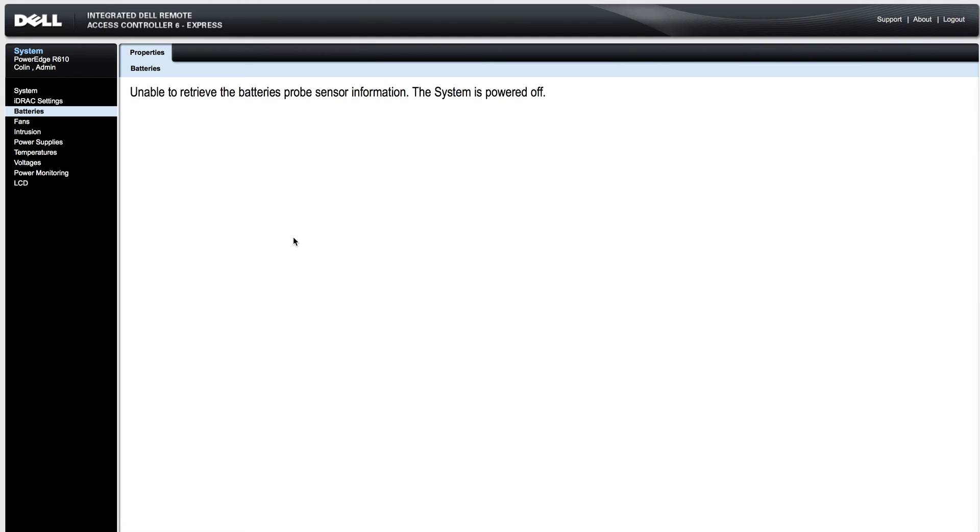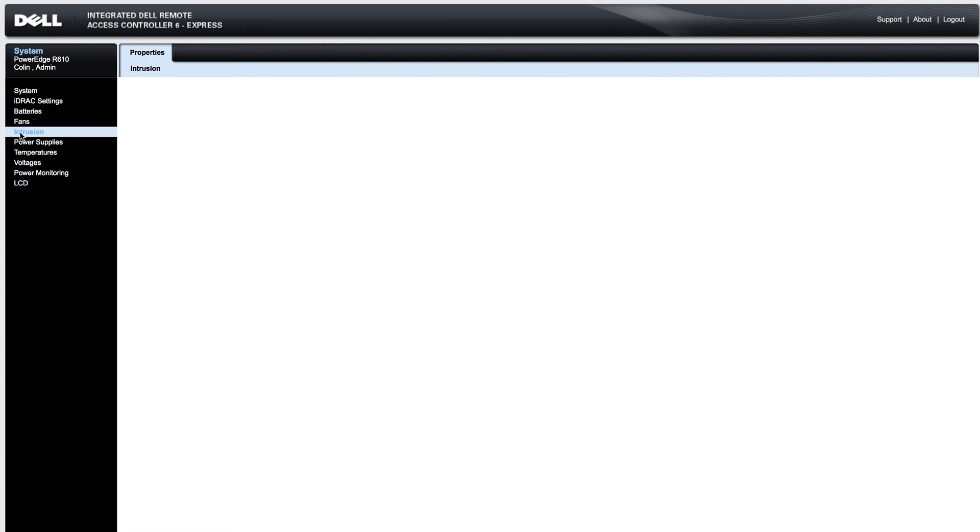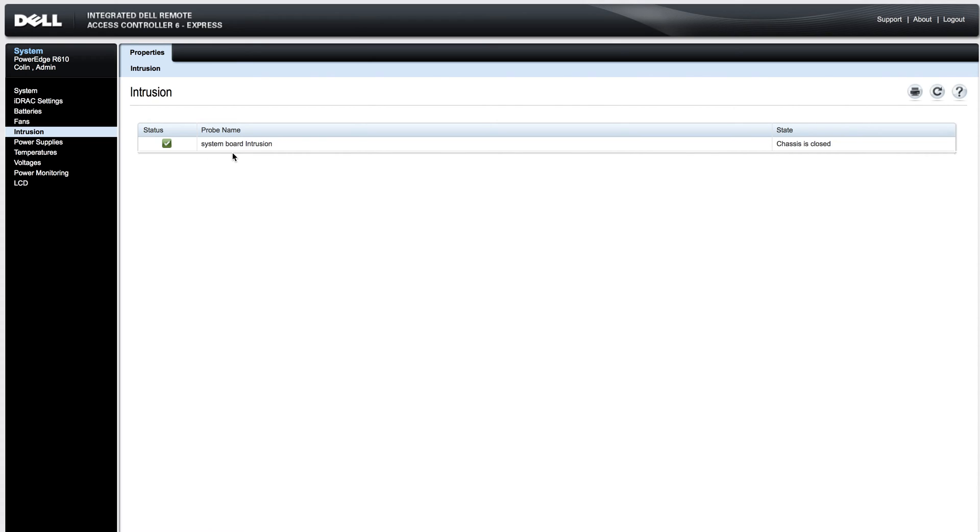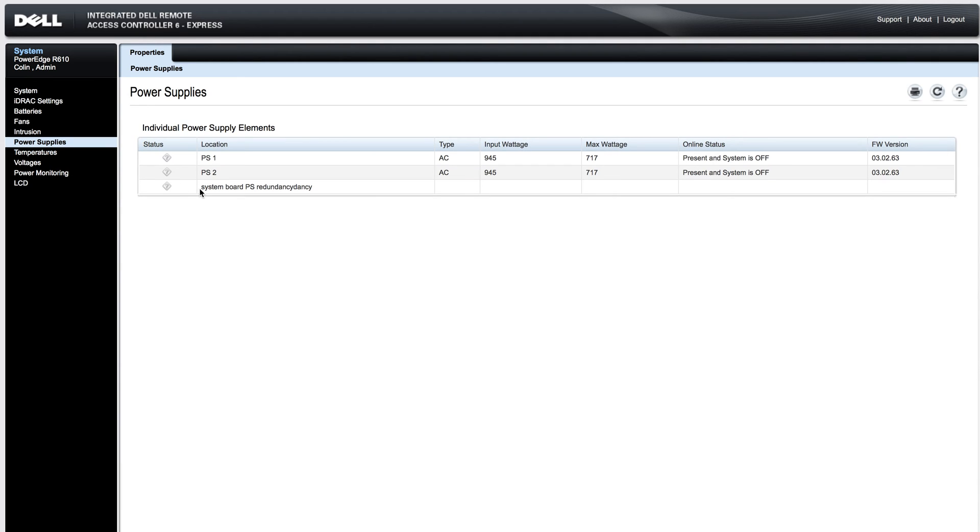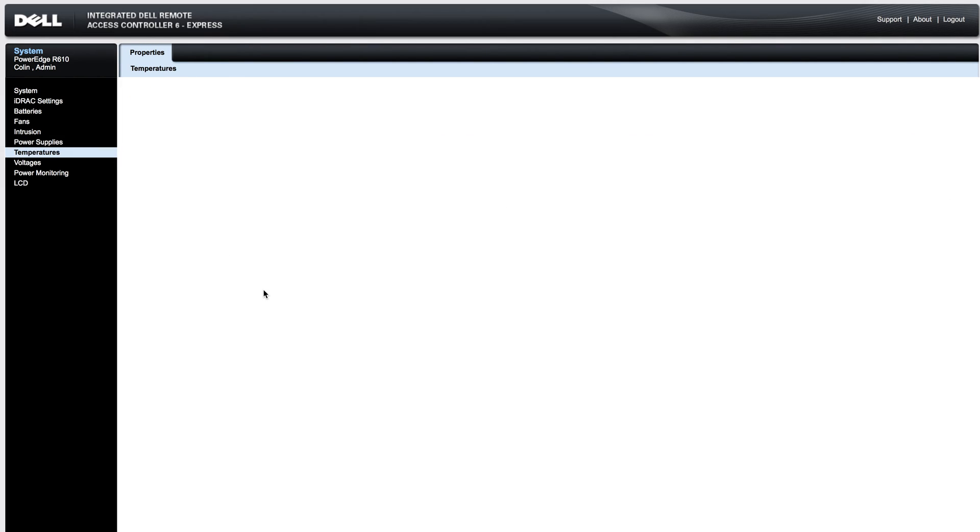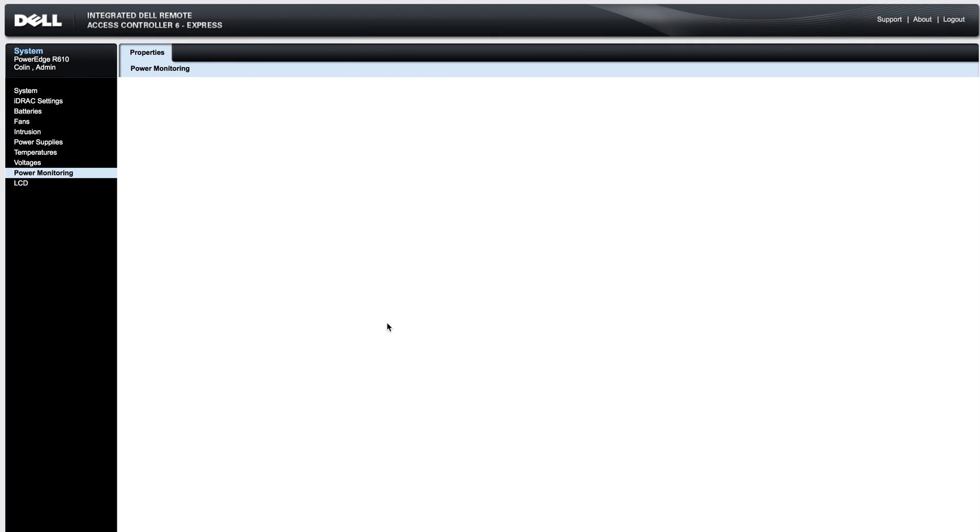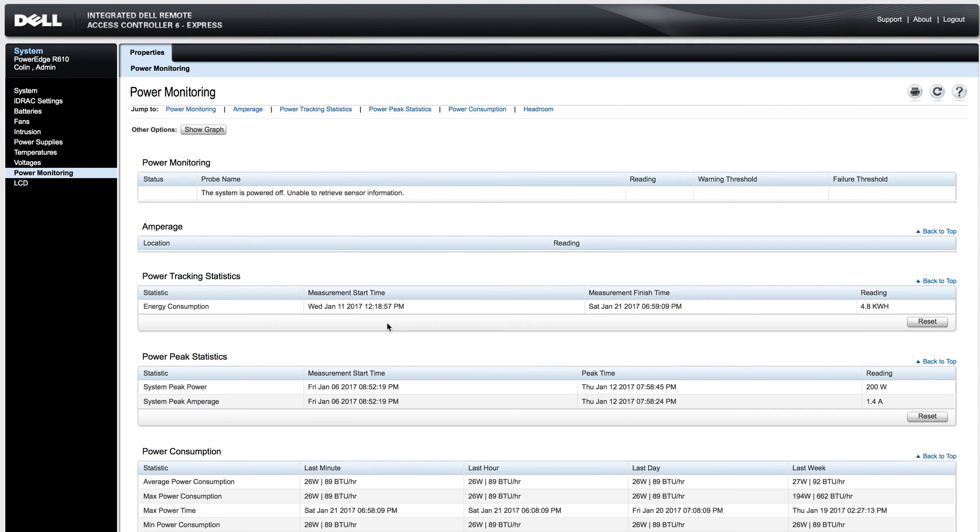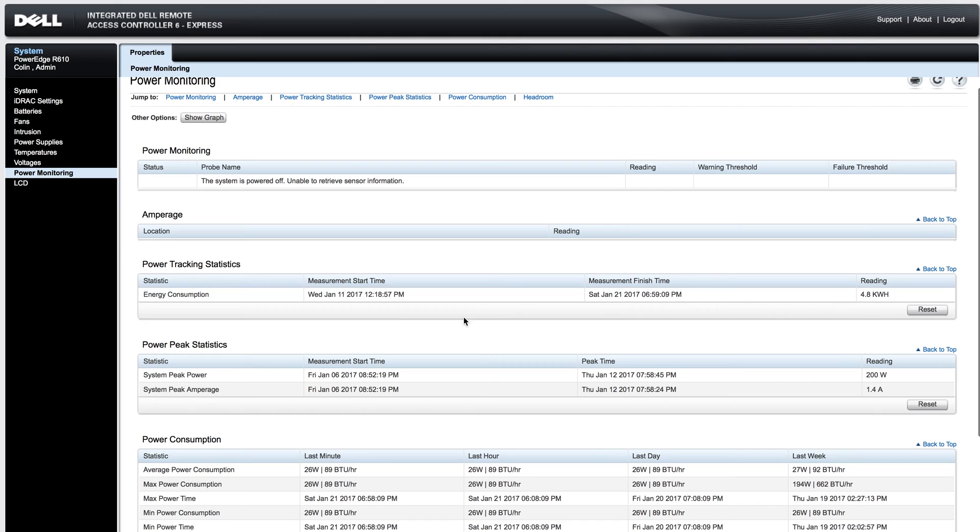You have battery information for the RAID controller, fan information for system fans, and intrusion information which will tell you whether the top case is open or closed. You have power supply information. It will not show anything other than present when the system is powered down. Temperatures will also not display when the system is powered down. All these sensors are offline when the system is powered down, so you will have to power up the system to view any of that information.